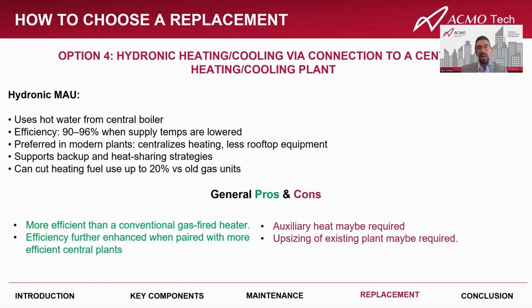Last but not least, a hydronic system uses the central plants of the condo, so your boilers and chillers, to provide that heating and cooling to the makeup air unit. If your cooling plant has recently been upgraded to a condensing system or high efficiency system, this becomes a great choice for replacement of the direct gas-fired unit with one that is hydronic, where you can tap into that higher efficiency of the unit from the main cooling plant.